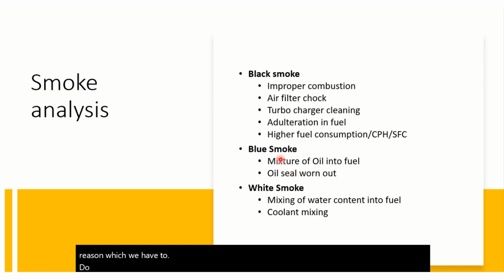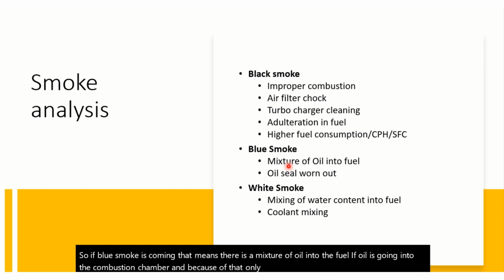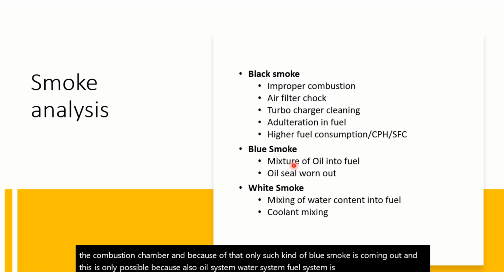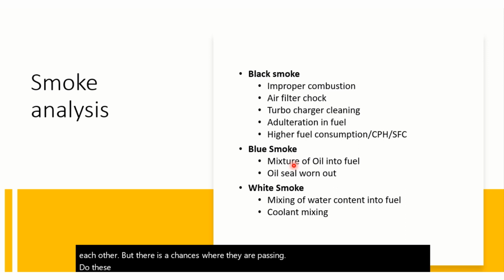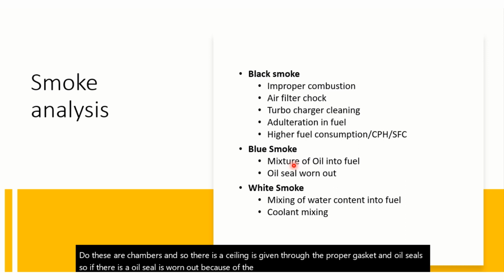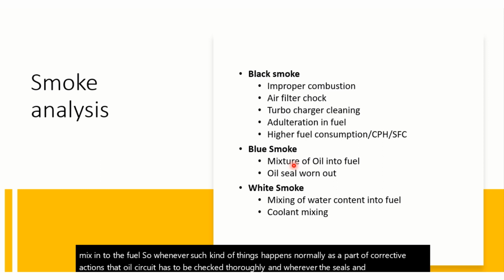do the correction. So if blue smoke is coming, that means there is a mixture of oil in the fuel. If oil is going into the combustion chamber, because of that only such kind of blue smoke is coming out. This is possible because the oil system, water system and fuel system are totally different from each other, but there is a chance that they pass into these chambers, so sealing is given through proper gaskets and oil seals. If an oil seal is worn out because of aging, then there is a chance that this oil can mix into the fuel. So whenever such things happen, as a part of corrective action, the oil circuit has to be checked thoroughly, and wherever the seals and gaskets are worn out, they have to be replaced.